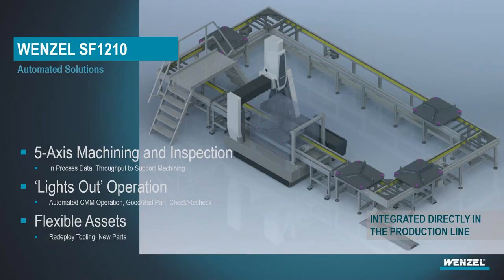Once again, the benefit of something like a WENZEL frame with the Revo is if you need to retool your line, if you were to, for instance, use hard gauges on the line, you would need to repurchase tooling, modify, change any gauging, and this type of thing. With something like the Revo 5-axis probing, at most you may need to change a styli tip or the length of a probe, but the entire system is there, operates very easily, and is very quick and easy to redeploy, even if you were to completely retool from a blisk inspection through to an engine block inspection within that automated cell.